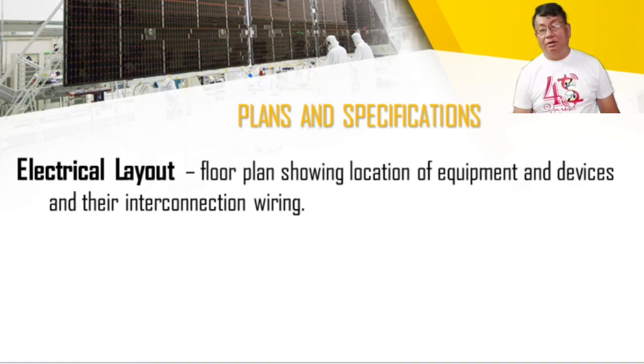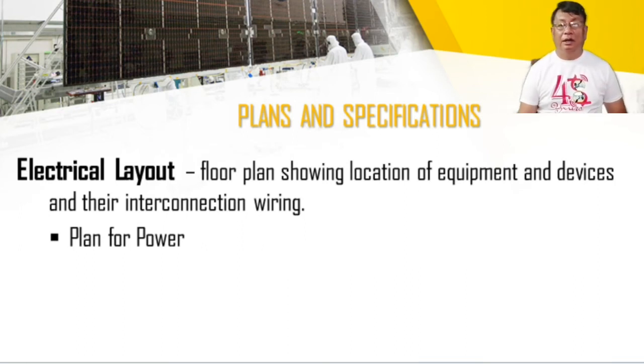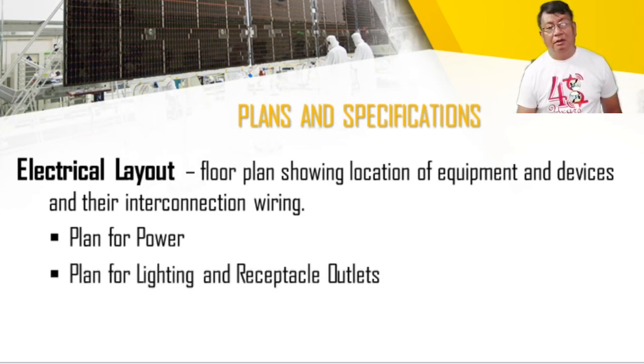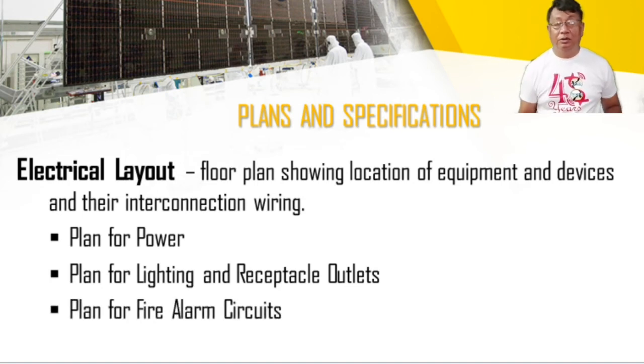Then we have the electrical layout, floor plan showing location of equipment and the devices and their interconnection wiring. We have the plan for power. Okay, you have the electric power. Then you have to plan where we are going to locate or place, no, or install. Plan for lighting and receptacle outlets. So we have this planning also for lighting and receptacle outlets. You have to design where to place it, and other locations, and we have to specify. Then plan for fire alarm circuit.